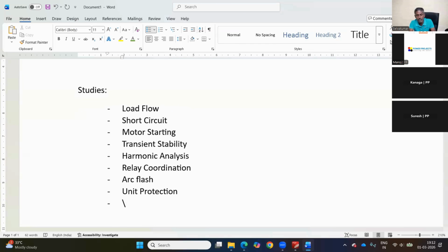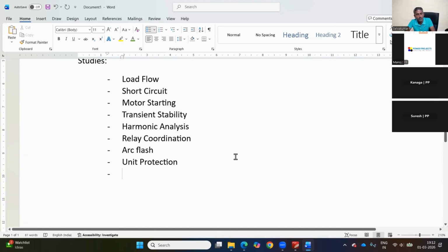the 110/11 kV transformer, and generator transformers. The generator, all those things, you need unit protection or equipment protection, like differential, restricted earth fault, etc. And for the 110 kV line also, if it is 3 kilometers, you need a differential protection. This all comes under unit protection.